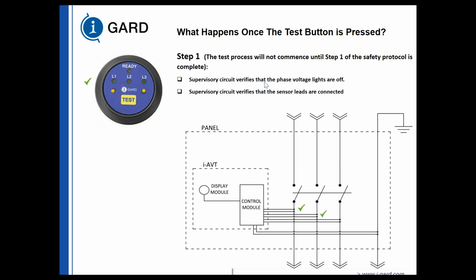The supervisory circuit verifies that the phase to voltage lights are off. Those 3 red LEDs are de-energized. Supervisory circuit verifies that the sensor leads are connected. So we perform a test to make sure that A phase, B phase, C phase, and the ground conductor are connected to where they're supposed to be connected. So we verified that the system is connected properly and there's no voltage present on the bus.